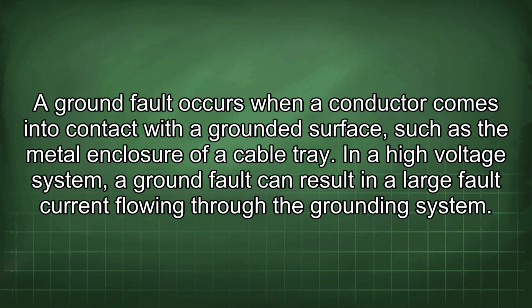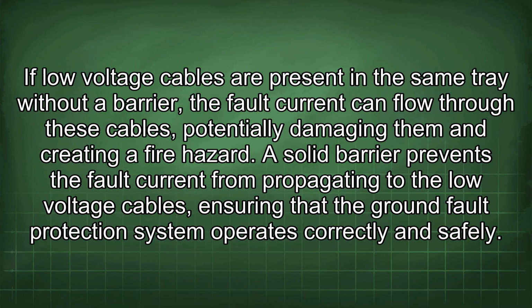A ground fault occurs when a conductor comes into contact with a grounded surface, such as the metal enclosure of a cable tray. In a high voltage system, a ground fault can result in a large fault current flowing through the grounding system. If low voltage cables are present in the same tray without a barrier, the fault current can flow through these cables, potentially damaging them and creating a fire hazard. A solid barrier prevents the fault current from propagating to the low voltage cables, ensuring that the ground fault protection system operates correctly and safely.